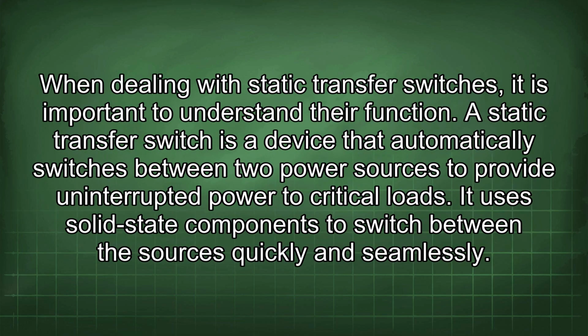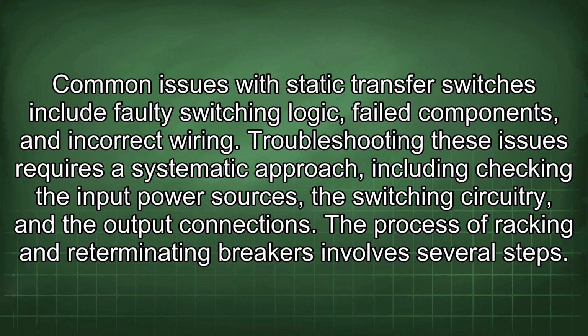When dealing with static transfer switches, it is important to understand their function. A static transfer switch is a device that automatically switches between 2 power sources to provide uninterrupted power to critical loads. It uses solid-state components to switch between the sources quickly and seamlessly. Common issues with static transfer switches include faulty switching logic, failed components, and incorrect wiring. Troubleshooting these issues requires a systematic approach, including checking the input power sources, the switching circuitry, and the output connections.